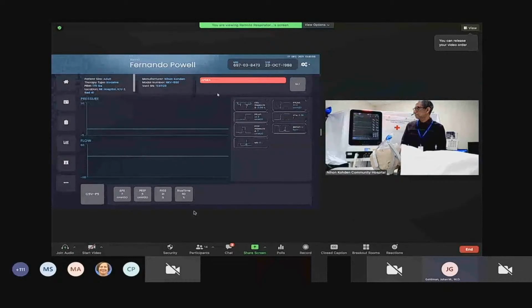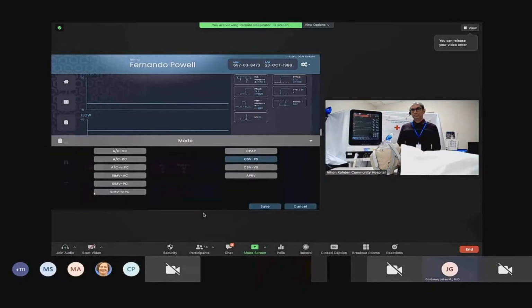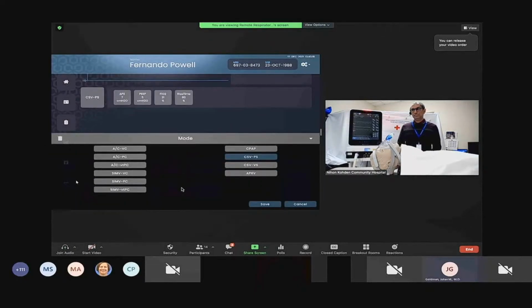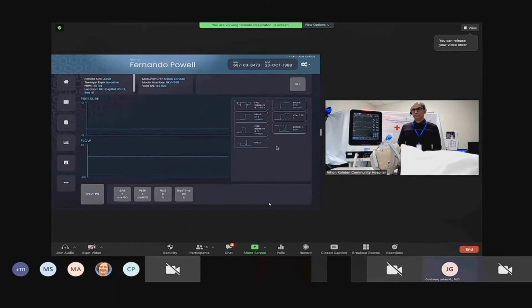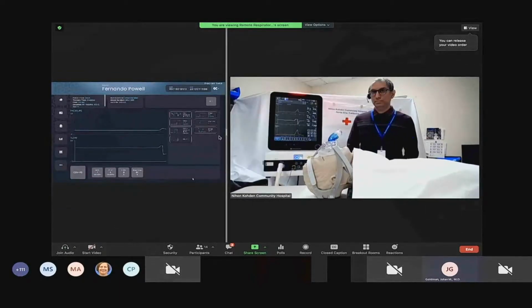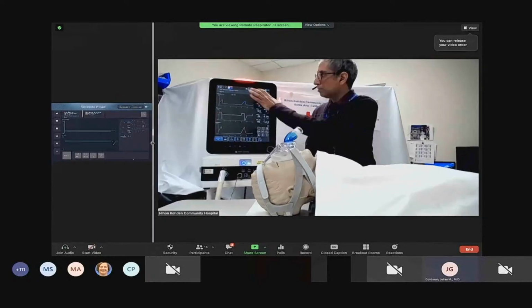You'll see on the DocBox system, we have that apnea alarm, like there is on the ventilator at Nihon Kohden. And we also have those flat waveforms that we see on the ventilator. All right, let's change to a mandatory ventilation mode. I'll come down here to the vent modes. Here are the available vent modes. AC, VC with volume control. Great, I'll select that and then save. Good. In a second, we should see the waveforms populate and the alarm turn off. It looks to us like the ventilator has been activated and is breathing for the patient.